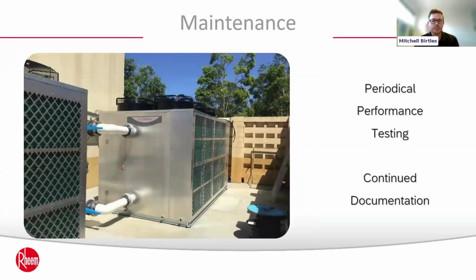Periodical testing of system performance and output can be monthly, bi-monthly, or quarterly, but it really should be regular. It shouldn't take much more than a couple of hours per unit with a qualified refrigeration technician or licensed heat pump service agent, if all that's happening are the standard checks and balances. They'll be ensuring refrigerant circuit performance, system motor effectiveness, water temperature differentials, and that the coils and fans are clear of debris.